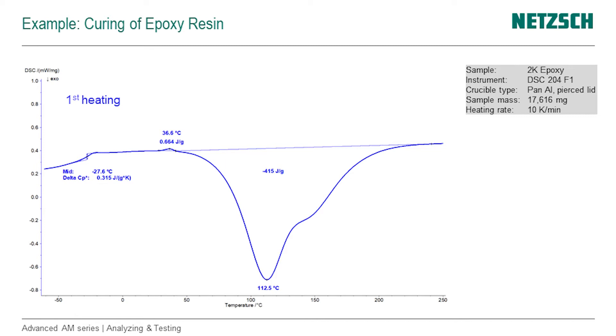So how does a curing reaction in a DSC look like? For a typical thermal cure material, like an epoxy, the curve looks like this. We have our DSC signal, or our heat flow, as a function of temperature. The first thing we see is that we have a glass transition temperature — the step change in specific heat capacity — and then we have the curing that's happening, and we have the release of heat. It's an exothermal process, so exothermal goes down.